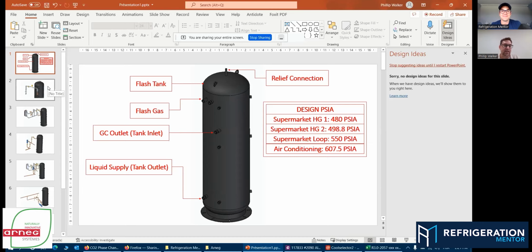And in Canada, at least, transcritical operation is not shied away from. We do a lot of heat reclaim, even throughout the summer. All supermarkets require dehumidification, so we're bringing the airstream down really, really cool. We use the heat recovery from the CO2 system to temper the air and bring it back up, so we supply neutral air to the supermarket space. So we're not shocking the customers.